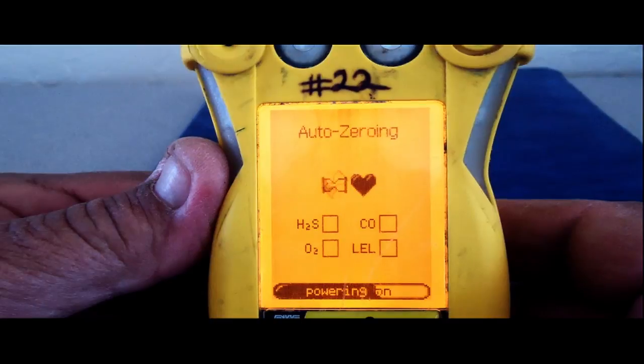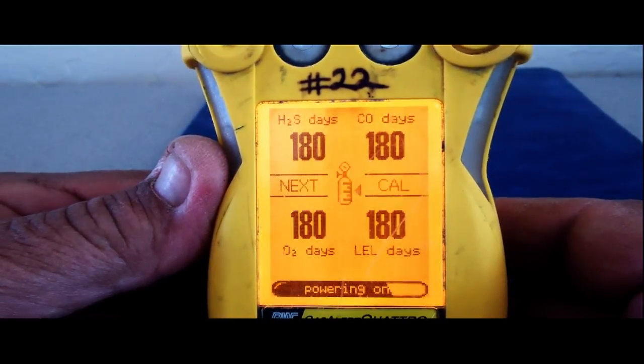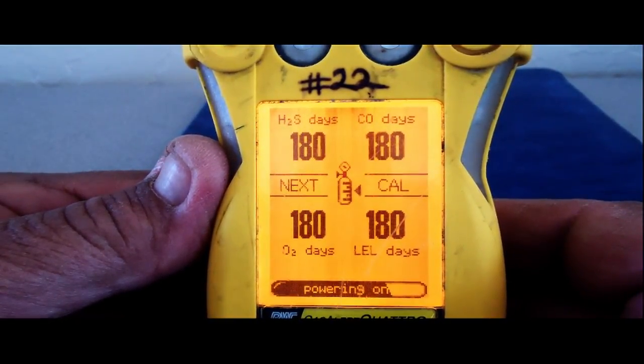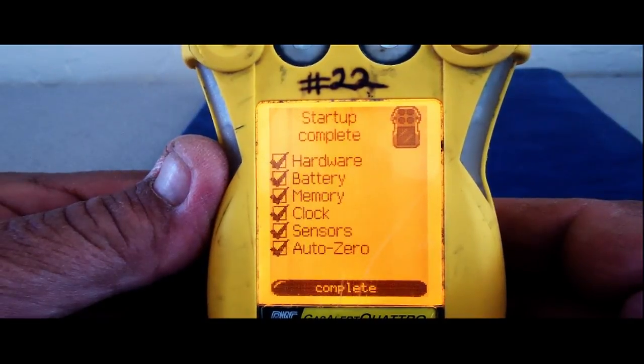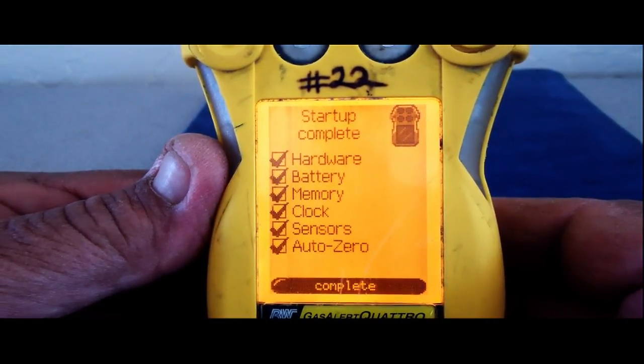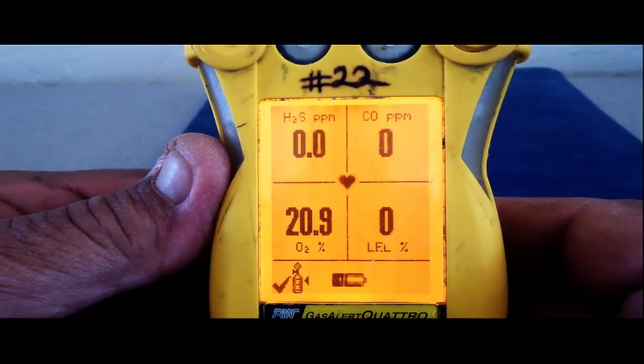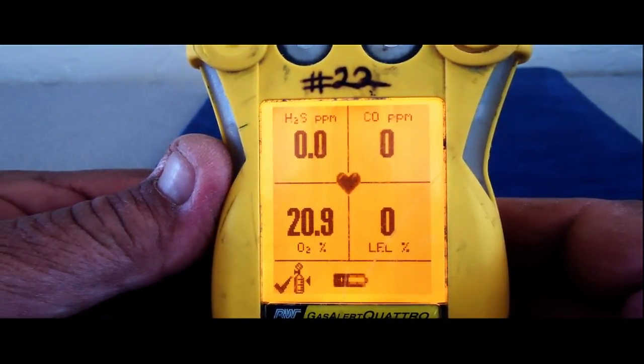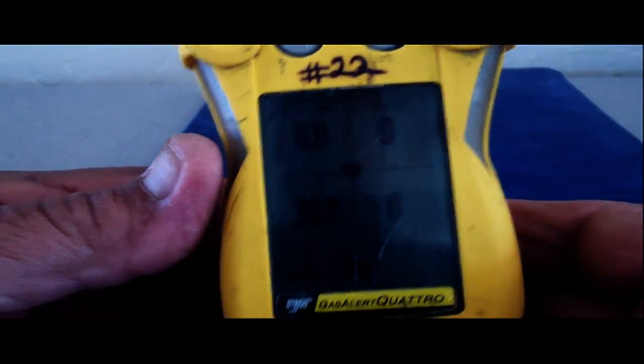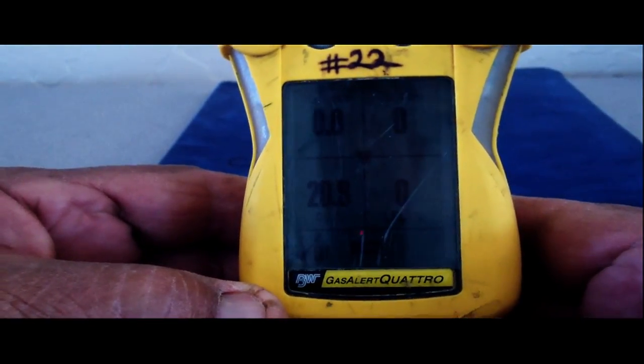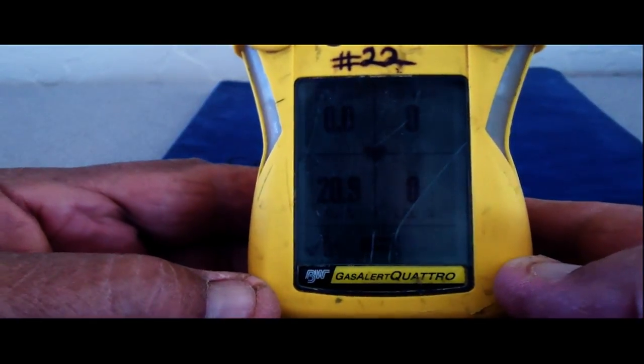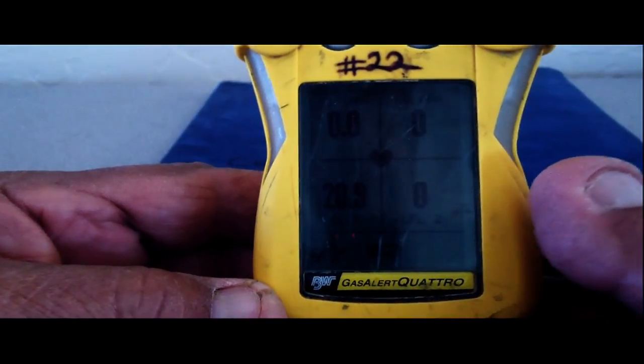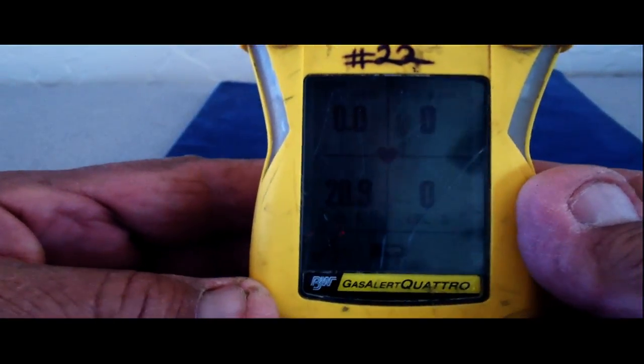So now it's going into its auto zero. So it's zeroing to the atmosphere that it's in. Make sure you're in a clean atmosphere when you start this thing up. Not by exhausts, not anywhere in a potentially contaminated atmosphere. So on the front of it, you'll see that the battery indicator is on there. Typically, a full battery is going to last you anywhere from 6 to 8 hours with this thing, is what we're finding. It's really convenient that you can change out those batteries in the field, and you'll find those in the case with all the meters and radios and harnesses.